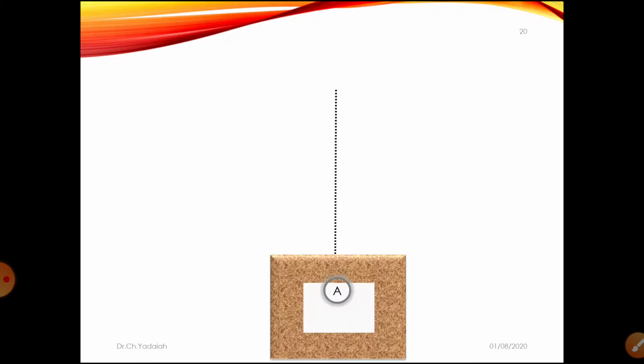Now dear students, in this case a length of just 2.4 meters is enough from ground level to the tip of the copper plate. 1.5 meters is the usual arrangement, plus nearly 90 centimeters depth. So the plate, 60 centimeters by 60 centimeters, is placed under the ground. Take the center line as usual and mark the plate size of 60 centimeters on this side.